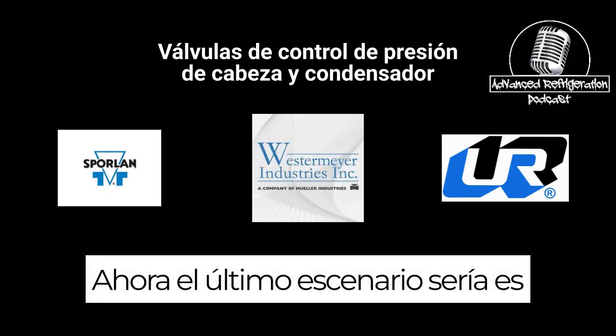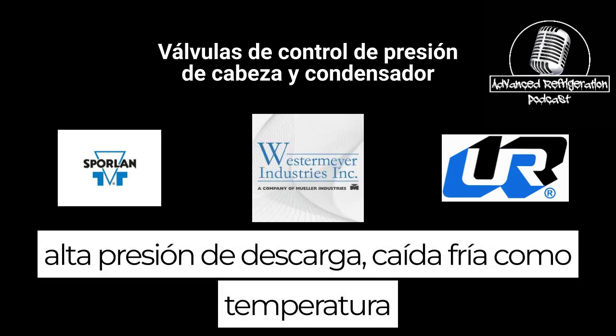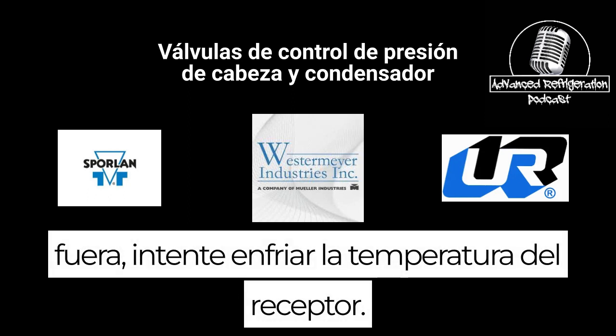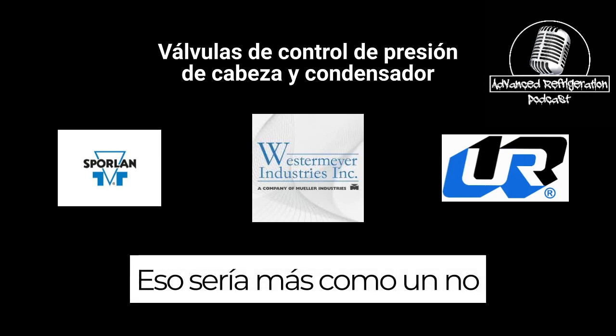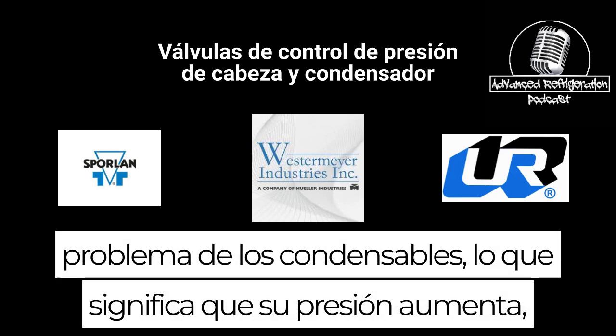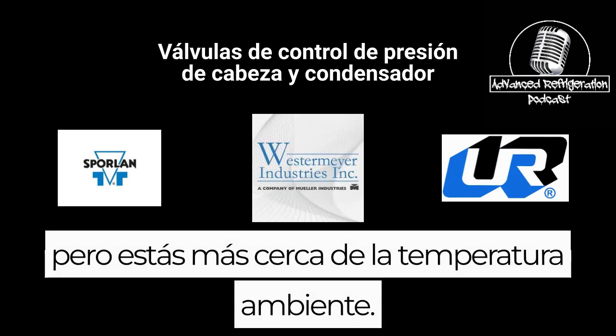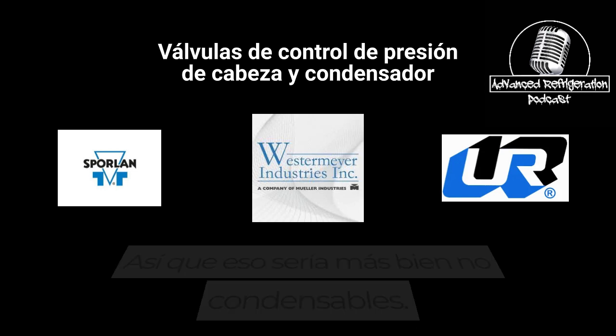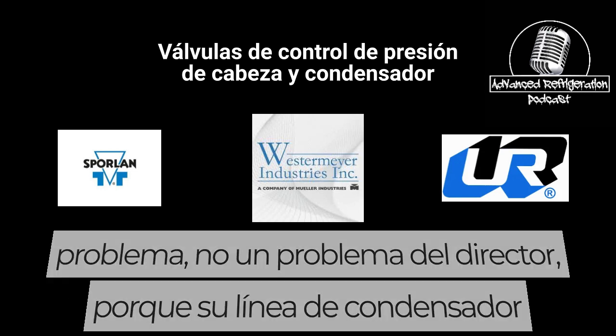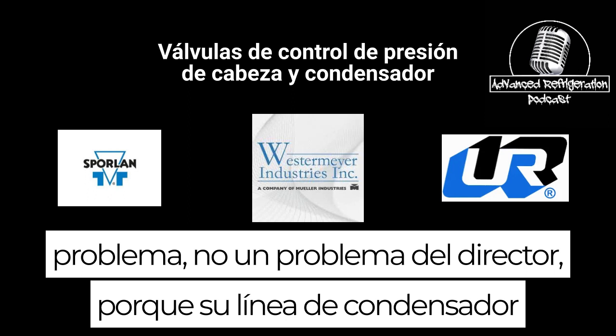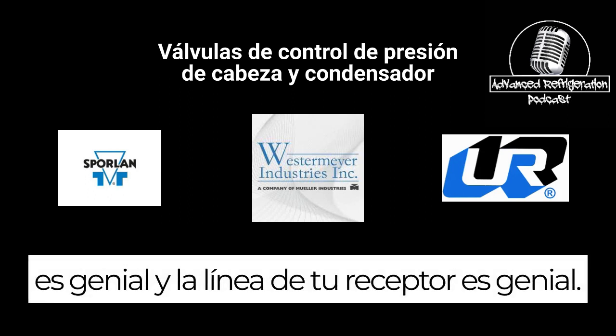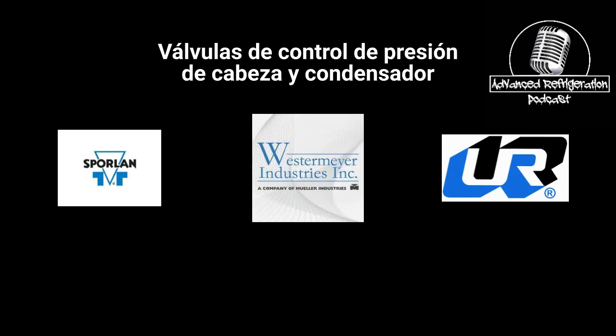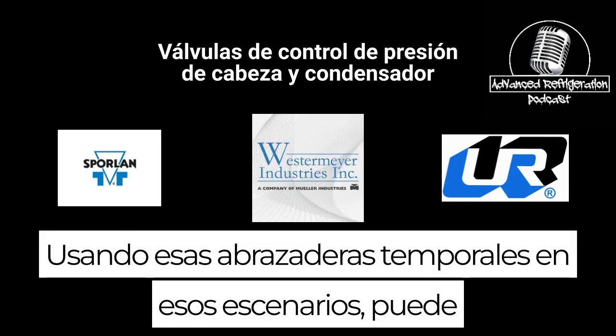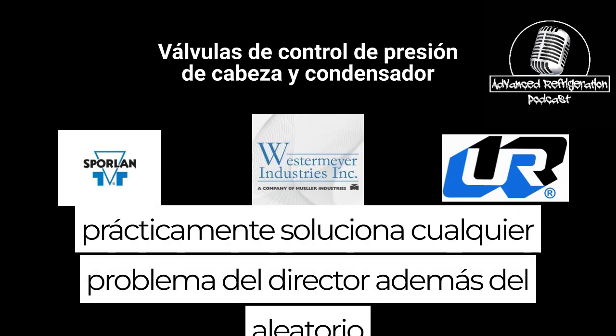Now, the last scenario would be high discharge pressure, with a cool condenser outlet temperature and a cool receiver temperature. That would be more of a non-condensables issue, meaning your pressure is raised up but you're closer to ambient temp. So that would be a non-condensables issue, not a headmaster issue, because your condenser line is cool and your receiver line is cool.